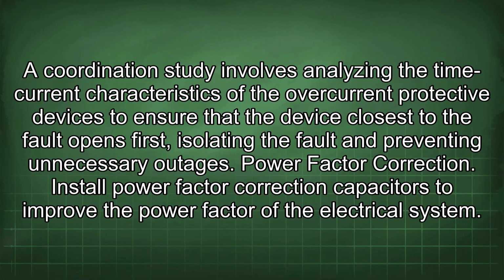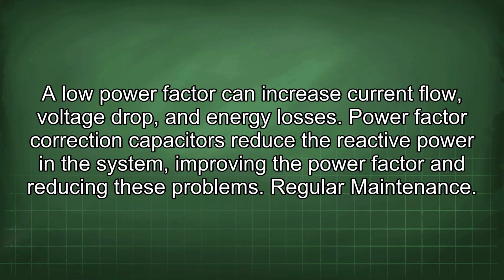Power factor correction. Install power factor correction capacitors to improve the power factor of the electrical system. A low power factor can increase current flow, voltage drop, and energy losses. Power factor correction capacitors reduce the reactive power in the system, improving the power factor and reducing these problems.